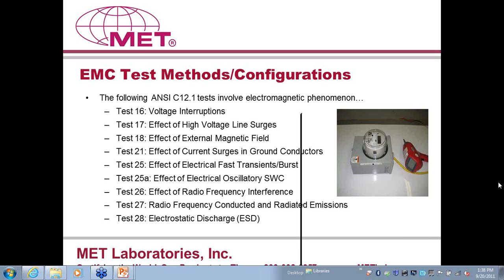Then there's test number 26, effect of radio frequency interference. This test verifies the immunity of the metering device when it is in close proximity of intentional radiators, say walkie-talkies or cell phones. Test number 27 is radio frequency conducted and radiated emissions. The intent of this test is to make sure that the emissions coming from the metering device meet the limits imposed by FCC Part 15B for a Class B type of device, or a residential device. Then there is test number 28, electrostatic discharge, which verifies the immunity of your equipment when it is subjected to static electric discharges, typically from operators.